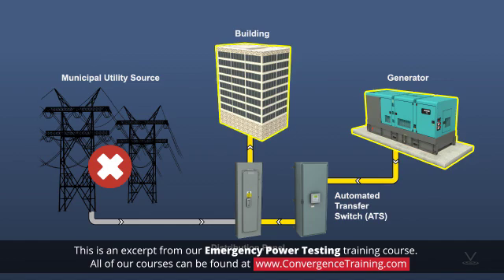The purpose of the initial 20 to 30 second delay is to assure that the utility dropout is not just a short-term glitch or power destabilization. If it is a real power interruption, the generator should start and take over the utility's power supply duties.